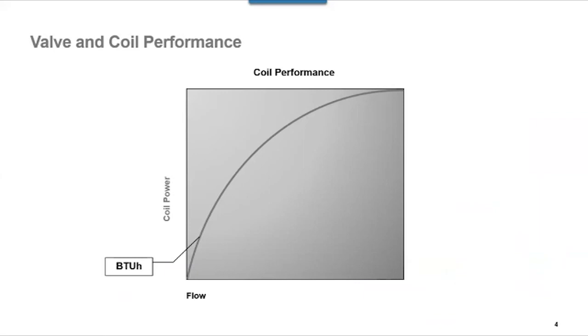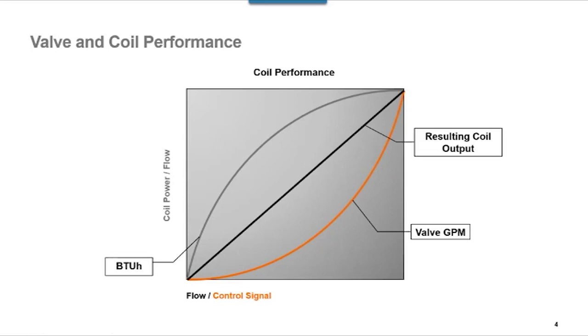Hydronic coils have a decidedly nonlinear characteristic. So to effectively control this nonlinear coil characteristic that you see on the screen there, engineers design and propose using an equal percentage flow characteristic valve. You look at this, it's obviously a mirror image of the coil. I put the two together, and now what I've done is basically taken that nonlinear coil characteristic and made it linear to make it much easier to control with a linear control signal. This is what you're trying to get with a pressure dependent control valve, but more importantly, this is the characteristic you get with a pressure independent control valve.